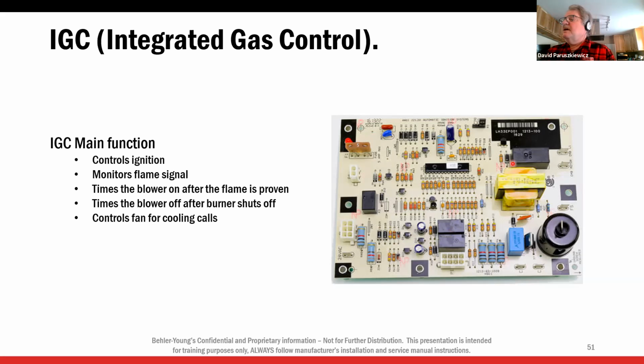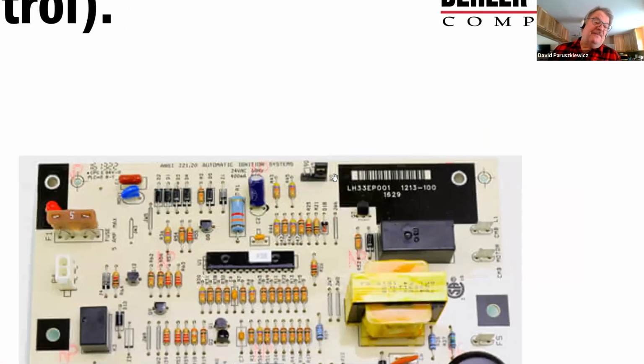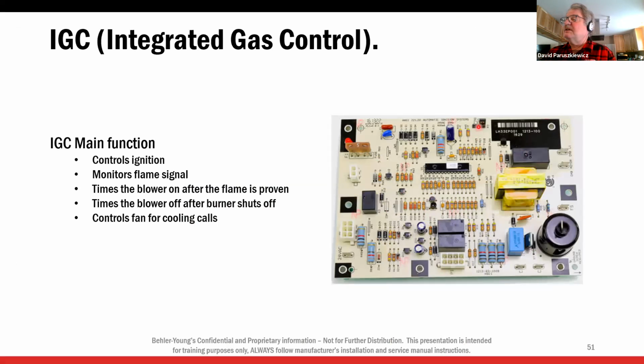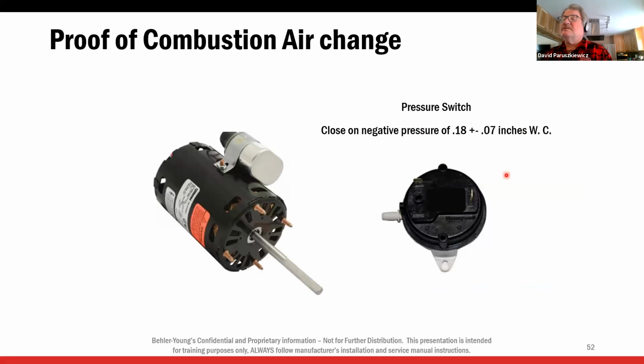All right. This little jumper over here, you all see, that is delay off for air conditioning. All right. There is no way for you to adjust the blower on and off speed for heating. Okay. That we cannot do. This little jumper is for cooling only. Has nothing to do with heating. All right. The 24 volts comes directly to this board first and through this little fuse. So if the whole unit appears to be dead, let's take a look at this fuse. Okay. So I just want to give you some heads up on this little board here. And for the most part, this is the same board on both units. Okay.